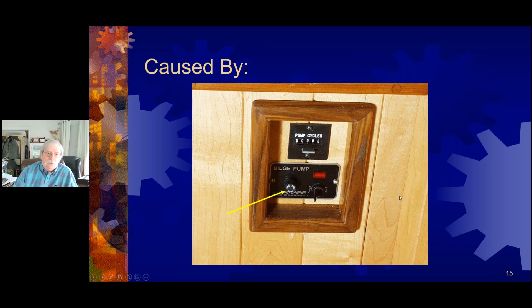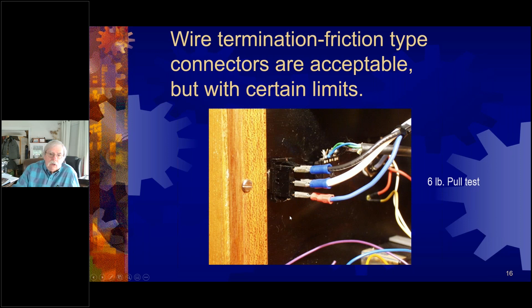Wire termination is important, and friction type connectors are allowed, but there is a 6-pound pull test. It's a requirement, and you're going to run into a lot of loose connections. I'll talk in a little while about ways that you can find that pretty easily. We require no more than 4 wires on a given stud, and this one they had a little trouble counting. They got it up to 6. I've got some photos that'll show up that are even worse or better examples.